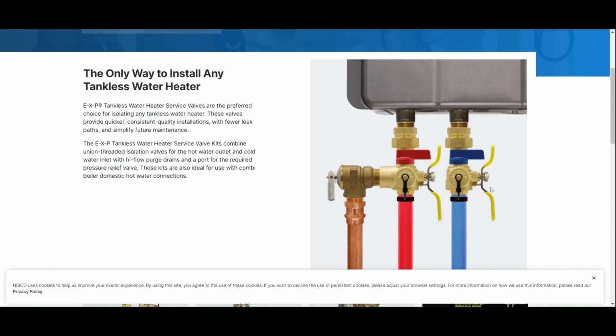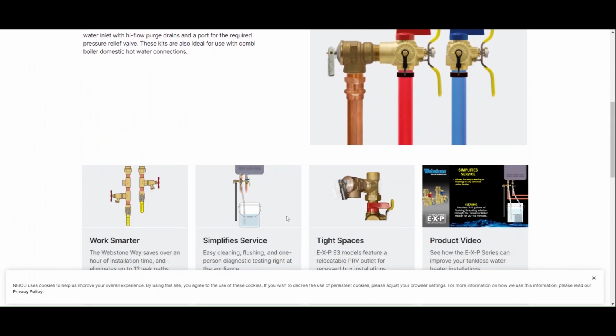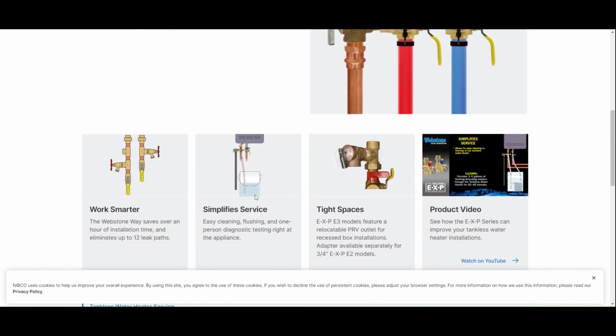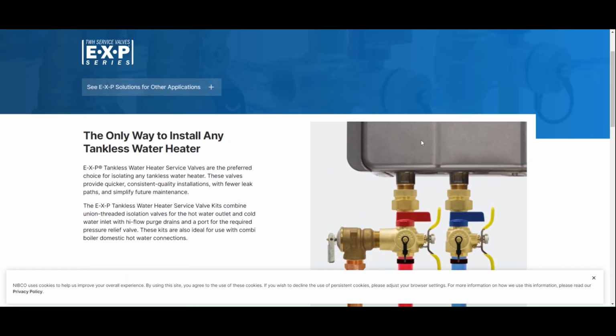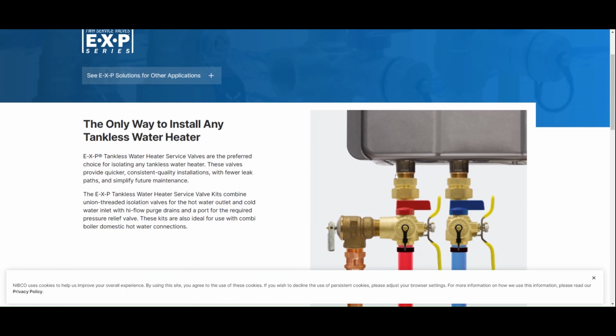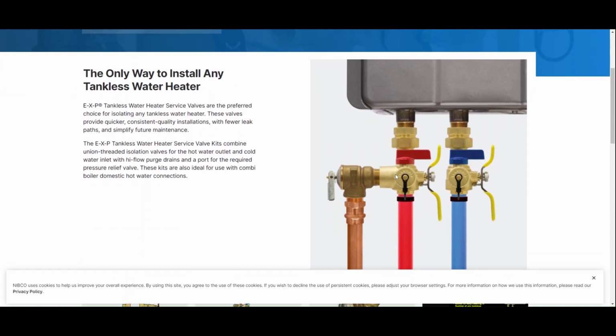This is the cold supply shutoff here, the yellow valve, and this is the hot supply shutoff valve here, again yellow. These here are the ISO part of the kit. So we can shut these two valves off, open these two valves, and then we flush muriatic acid or vinegar, cleaning vinegar through here. So you can kind of see it in this little picture here. It gives you some kind of an example, but basically you flush from one side of the bucket to the other, and that removes scale from the heat exchanger. So one of the other ways that I see shortcuts, and then you can't do maintenance in this area.